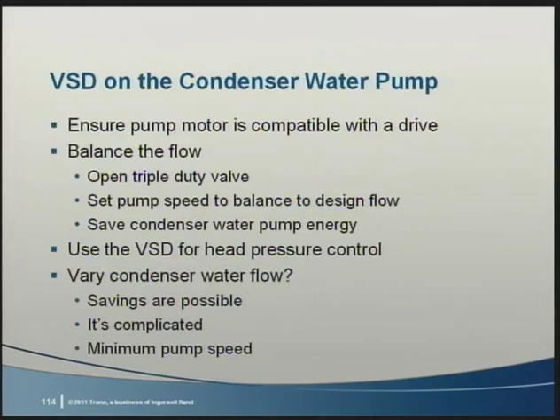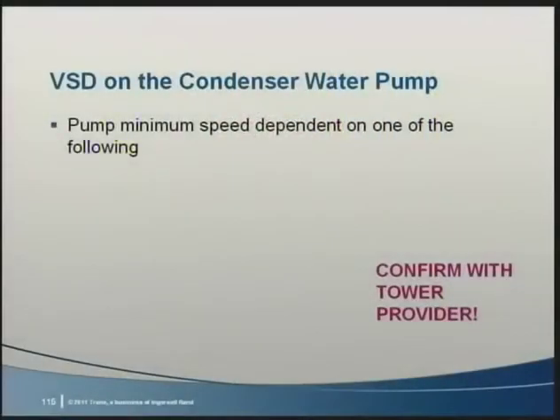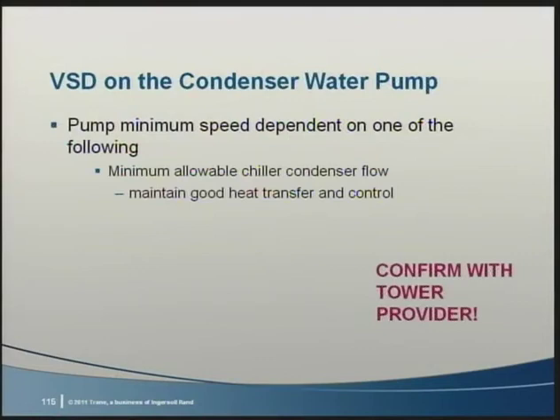There are possible savings, but because of all the changes, it's complicated and there's a minimum pump speed. Let's look at that first. One thing to note is that the minimum pump speed may be set by one of 3 limits. It may be at the minimum allowable flow rate through the chiller's condenser. The chiller minimum is required to maintain good heat transfer and chilled water temperature control.